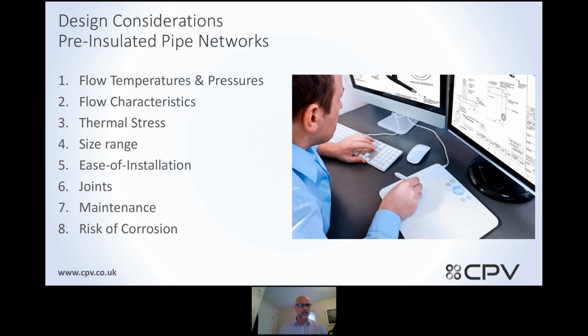Starting off with design considerations for insulated networks. The key areas are flow temperatures and pressures, which is usually the deciding factor for what material you use. Then you need to look at the flow characteristics. Will it take the flows that I need? Thermal stresses of the system. Do I need to take any stress analysis into consideration for expansion? Pipe jointing, ease of installation, areas on leak detection systems on pipework systems is the joints. So if you can reduce the amount of joints, happy days. Maintenance of the systems, and then the risks of corrosion, which is quite crucial on these systems.